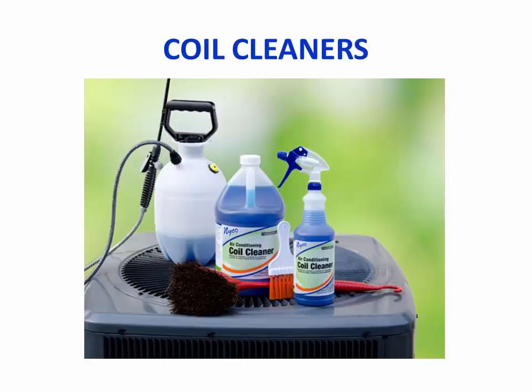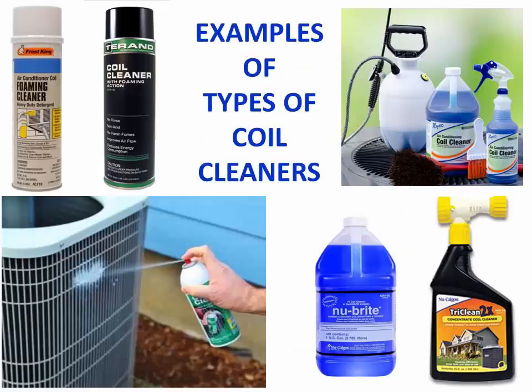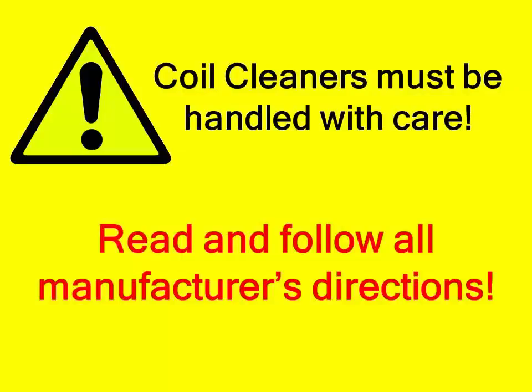Many manufacturers make coil cleaning products to aid in dislodging the contaminants on the coils. Some coil cleaners come in foaming aerosol cans. Others are liquids or powders that must be mixed with water and used in a pump sprayer. Still others are solvent sprays. Note, all types of coil cleaners are strong chemicals and should be handled with care. Carefully read and follow the manufacturer's directions to provide the best results.